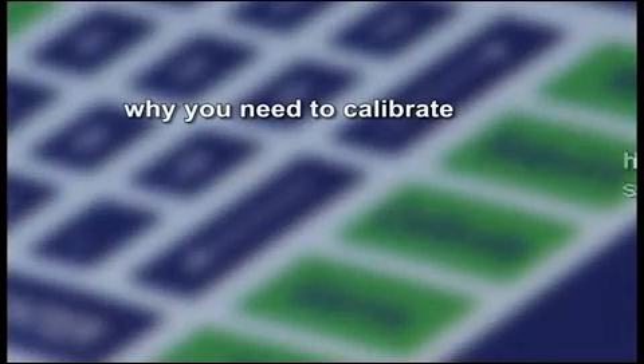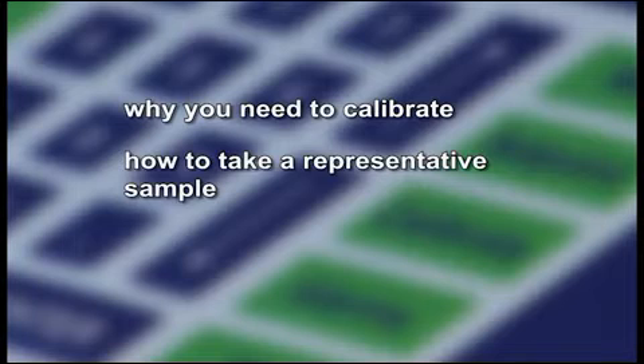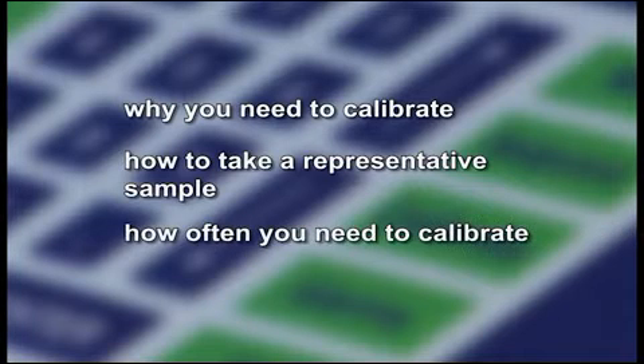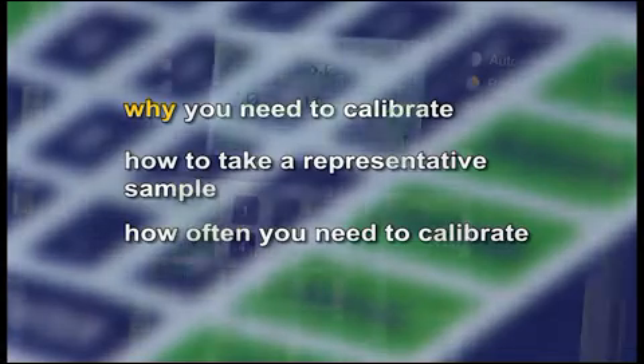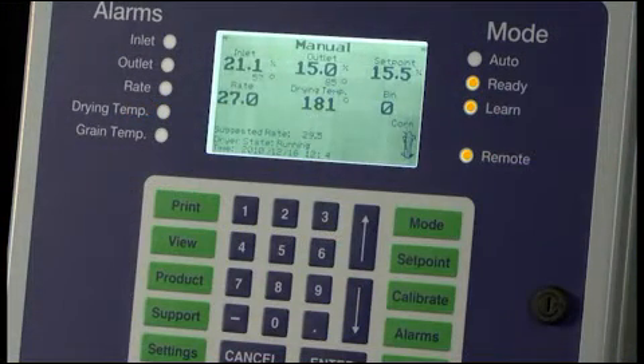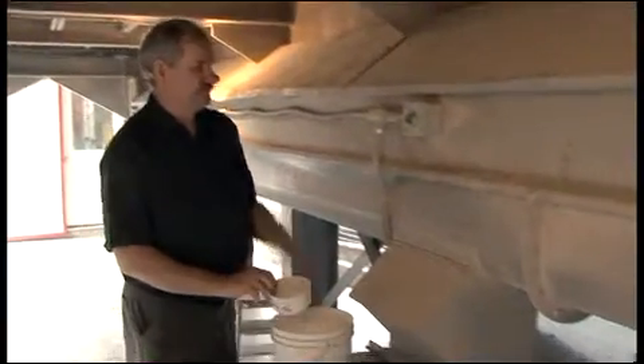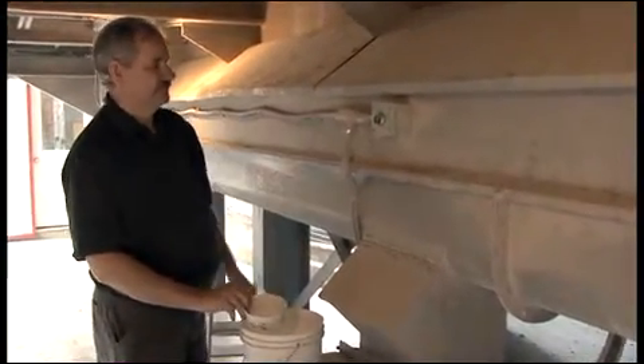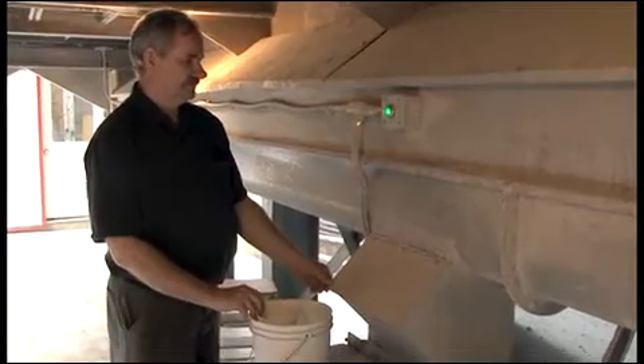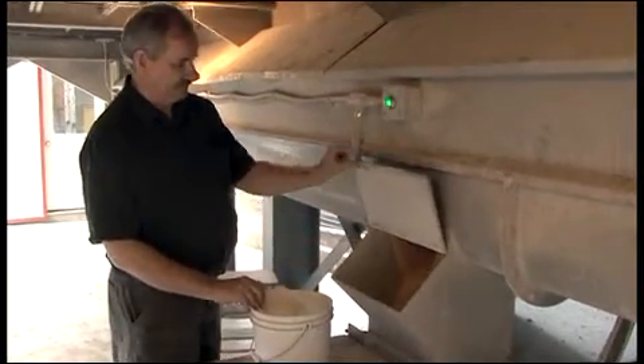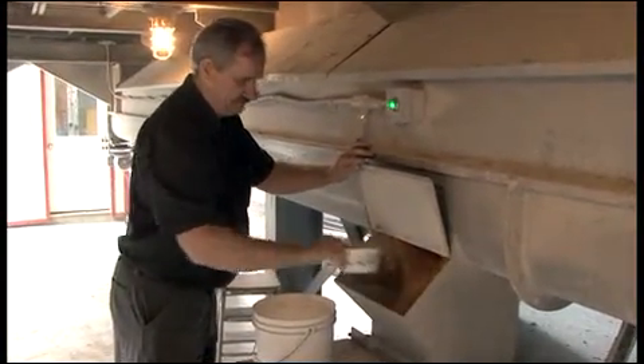In this section, we will talk about why you need to calibrate, how to take a representative sample, and how often you need to calibrate. Why? While it may sound straightforward to have the online moisture sensor read the same as your benchtop unit, there are a few wrinkles that make it a little more complex. Let's look at an example where an operator goes to the dryer and takes two moisture samples 20 seconds apart and puts them into two separate containers.